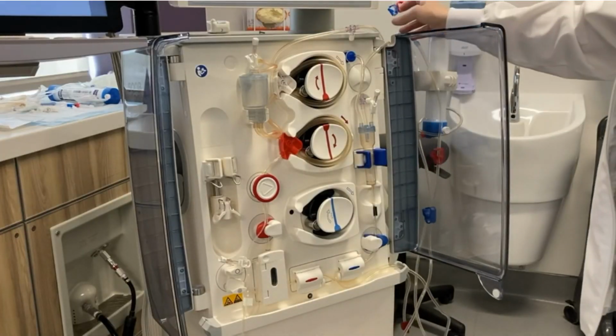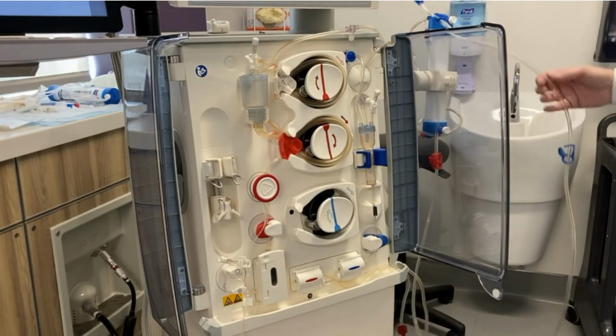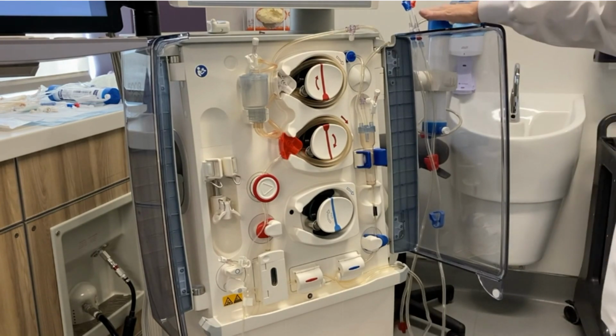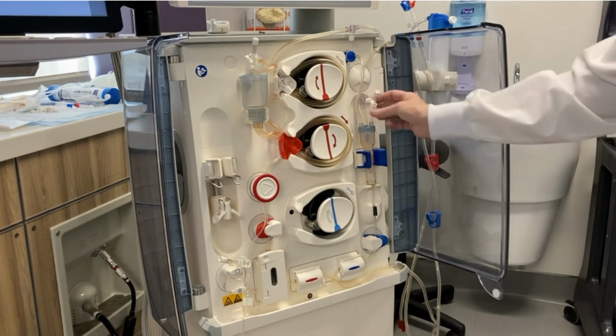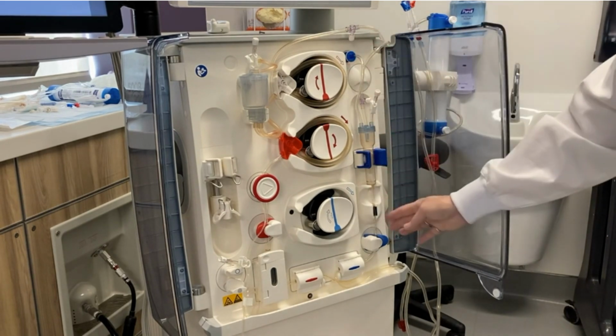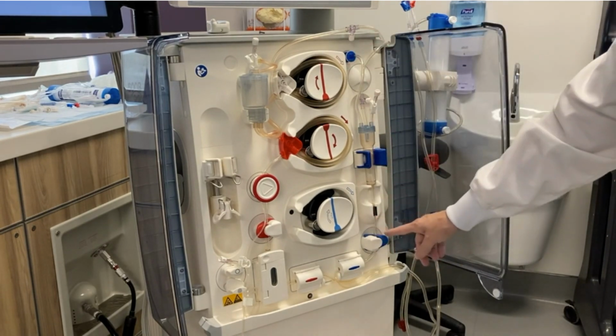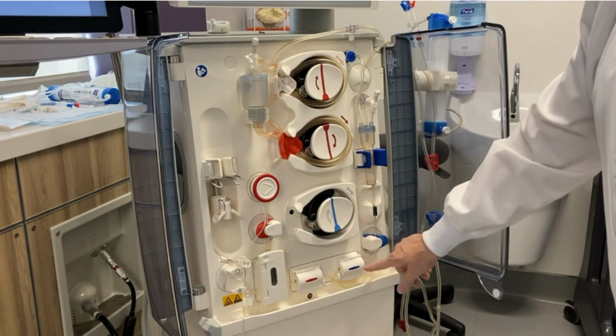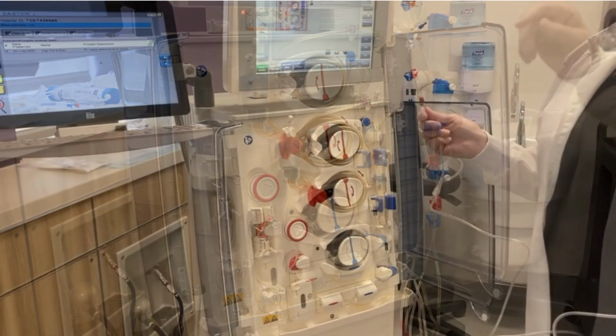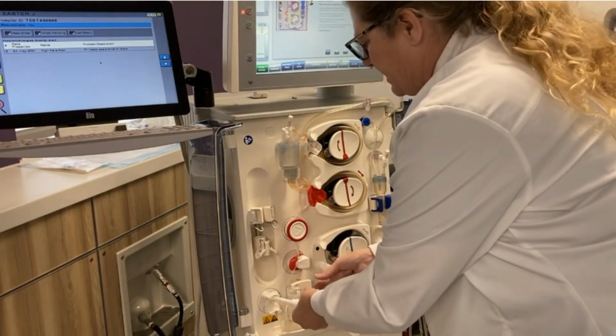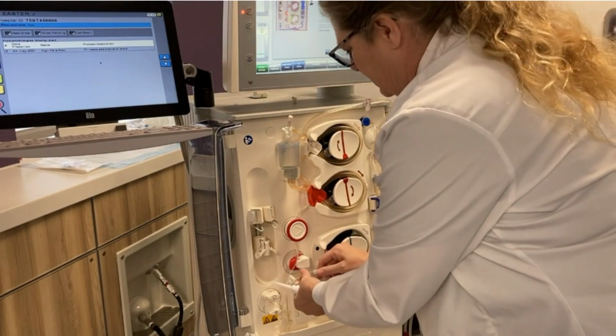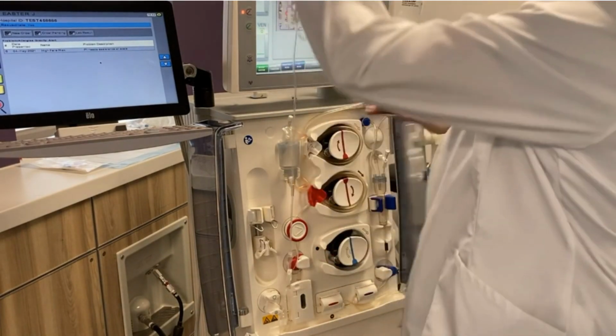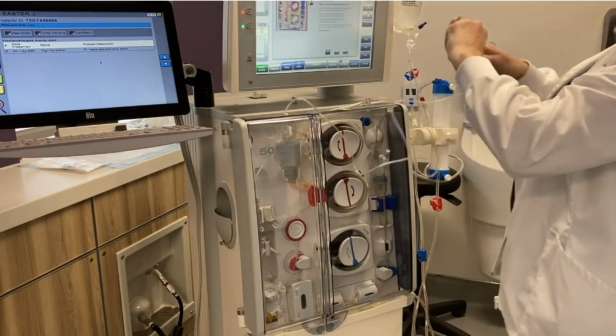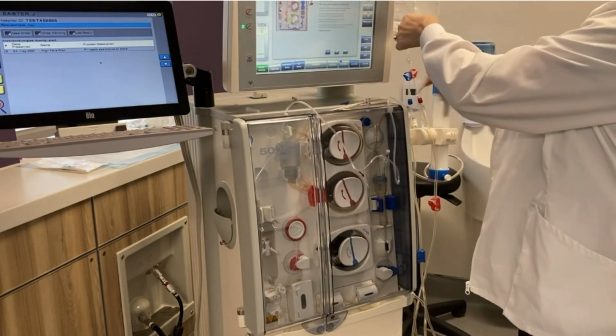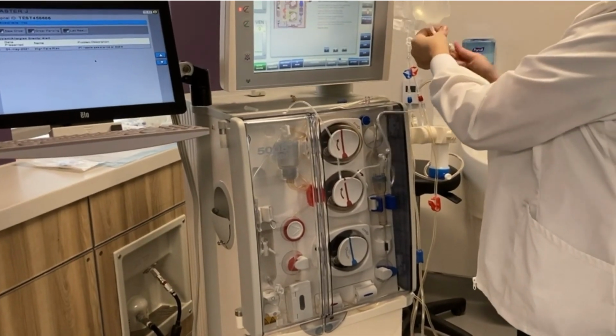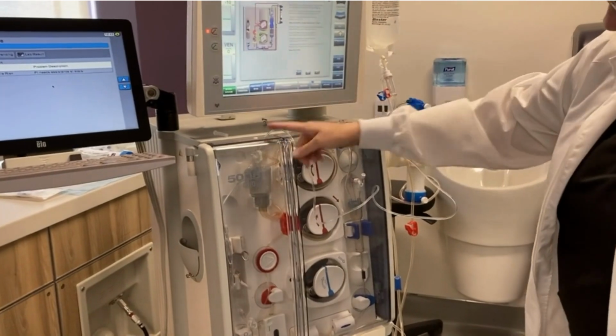So just for a review of the venous section, you've got your venous going to the dialyzer, you've got your venous bulb with your clamp on, your transducer, going through your air detector, your venous clamp, and your venous temperature monitor. So last step is connecting your saline, just as for your standard setup. We're going to connect it to the saline bag, and it's going to fill by gravity.